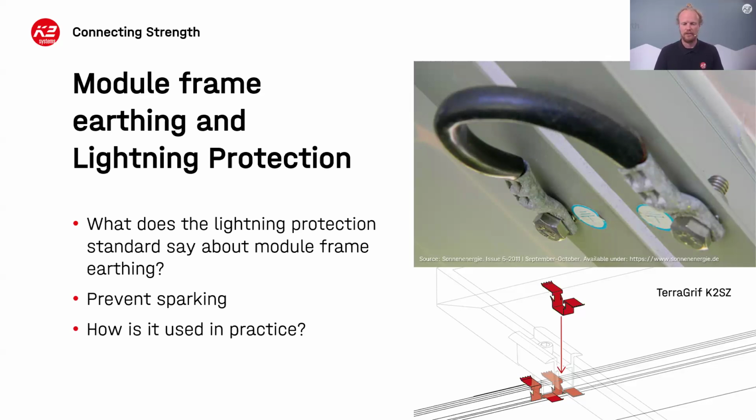Just on the cable, before we move on, it's not yet a rule, but it could be something that comes in the future, that this cable has a 6mm cross section, and the sole purpose of this cable must be for the electrical connection. So it's not allowed to have any mechanical properties or mechanical role within the system.